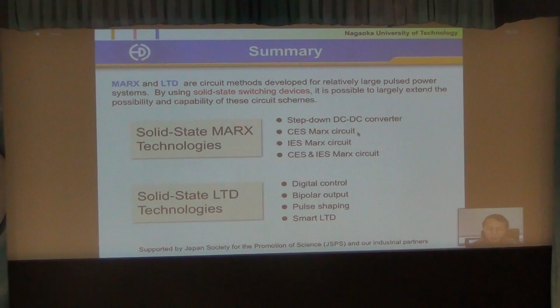This is a good question, depending on which one you're talking about. For the IES circuit, there's no problem, as we know, because it's inductive energy storage—there's no problem with a load short. But for CES, it's always an issue. If the load impedance is too low, we may have overcurrent on the switches, so we have to have special separate protection for CES Marx generators.